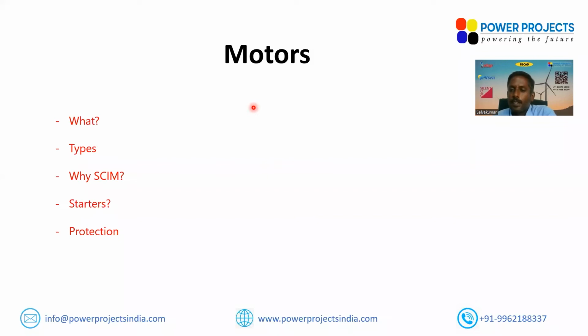Anything else? You can probably use a variable frequency drive. The input power factor of the variable frequency drive is unity. Your motor draws the reactive power from the variable frequency drive, but the variable frequency drive does not draw any reactive power from the upstream. Probably this technology is available in the variable frequency drive.